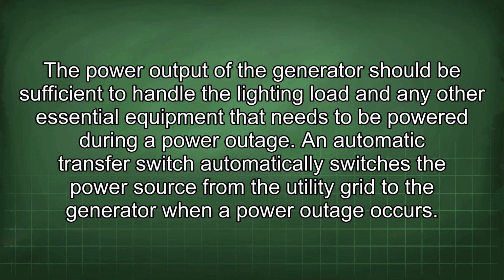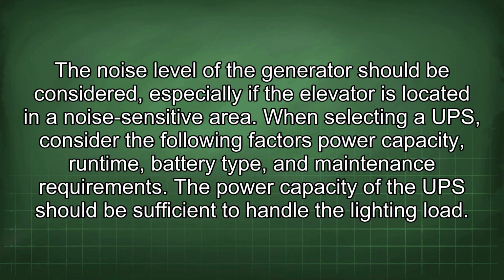An automatic transfer switch automatically switches the power source from the utility grid to the generator when a power outage occurs. The noise level of the generator should be considered, especially if the elevator is located in a noise-sensitive area.